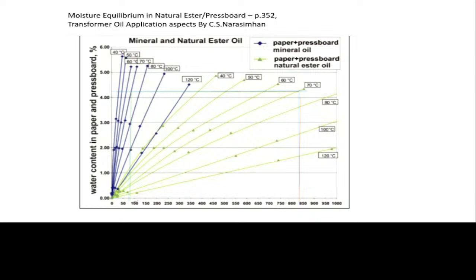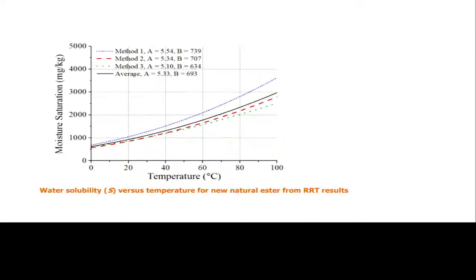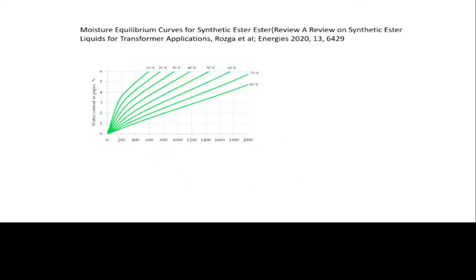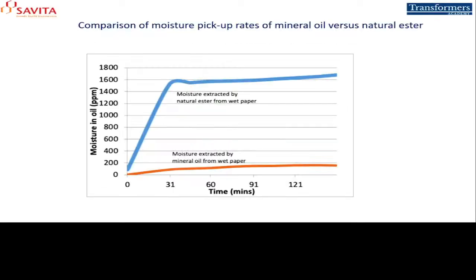But whereas in the case of ester oil, you can go all the way up to 950 ppm or close to 1,000 ppm. At 4% moisture on the paper, you have got a very wide bandwidth. The bandwidth for accommodating moisture is very high for ester oil. That is shown here in this comparative equilibrium diagram. So the same thing holds for the synthetic ester. The bandwidth available for synthetic ester is much broader because it can accommodate more moisture. Okay, these are all based on the equilibrium diagrams.